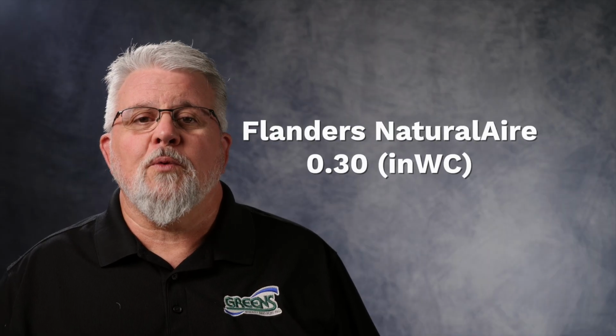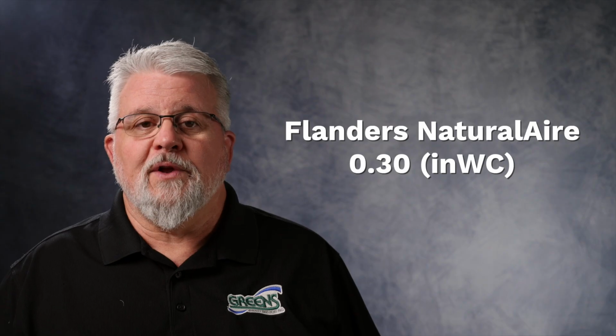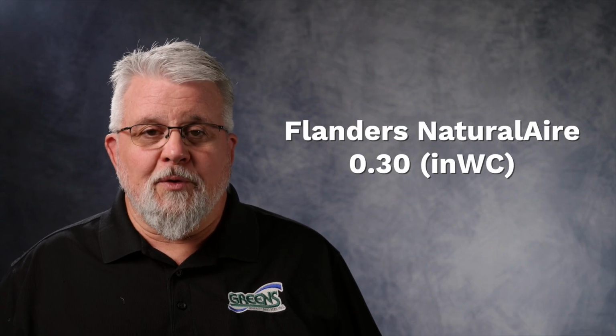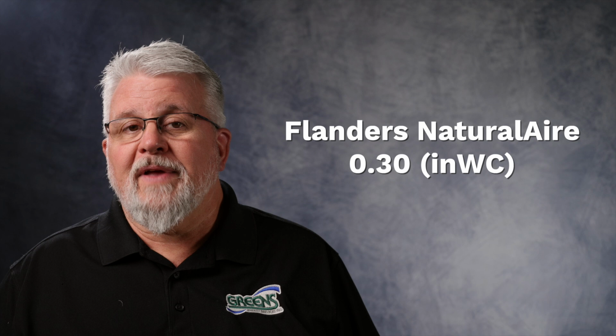Next up was the Flanders Natural Air Filter. This is also a MERV 8 filter, and I'm going to say, as far as rigidity, it's about the same as the Home Depot filters we tested. This filter is marketed as an odor-reducing filter because the media is treated with baking soda. But despite the stronger construction, the pressure drop increased quite a bit. I measured 0.30 inches across this filter. That's almost double the restriction of the HDX MERV 8 filter.